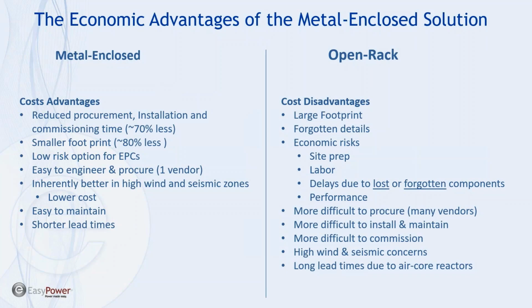On an open rack side, it's just simply not the case. When you buy an open rack solution, you're purchasing reactors, capacitors, switches, CTs, a control system, and somebody has to integrate that work. So you have to add cost in for that, and that can be significant. There's also a time issue. Metal-enclosed systems will install in about 70% less of the time period that it takes to purchase and install an open rack system. So from a time standpoint, when time is an issue, always consider a metal-enclosed system.